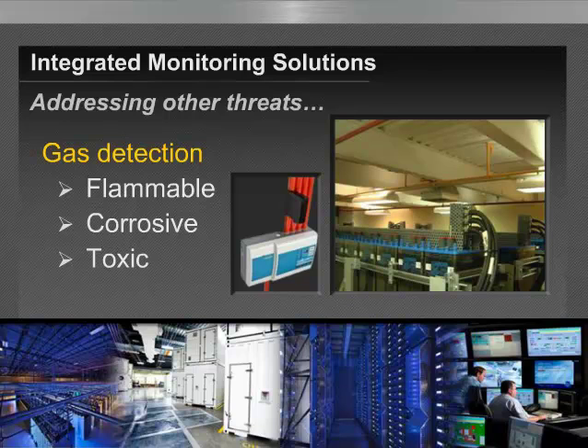to have a distributed sampling arrangement to detect in such spaces as battery rooms, cable vaults for methane, battery rooms for hydrogen, and other configurations where hydrogen, oxygen, or the corrosive gases, or for that matter, the toxic gases may be of concern, simply by utilizing the pipe network, adding a simple module onto it, and having the expanded capacity to monitor for various gases.